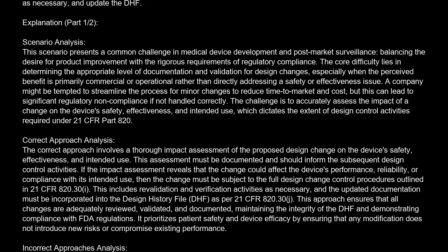The correct answer is A. Conduct a documented impact assessment to determine if the change affects the device's safety, effectiveness, or intended use. If it does, implement appropriate design change control procedures, including verification and validation as necessary, and update the DHF.